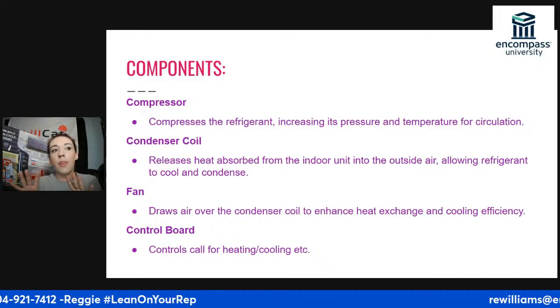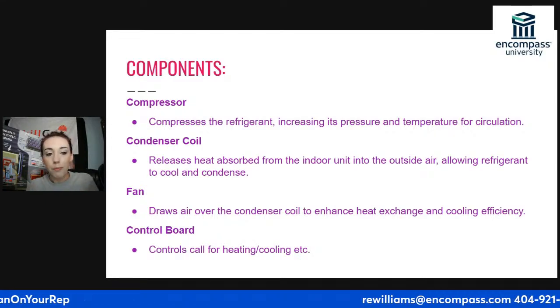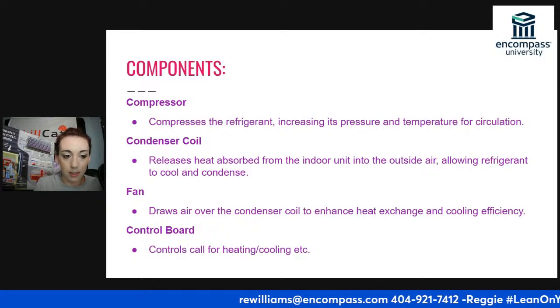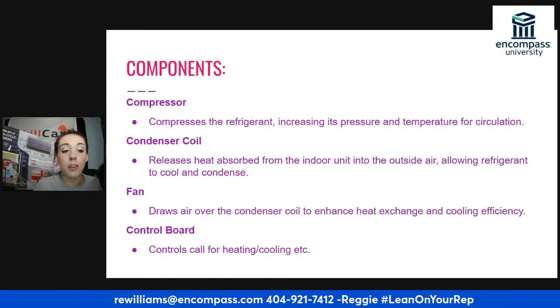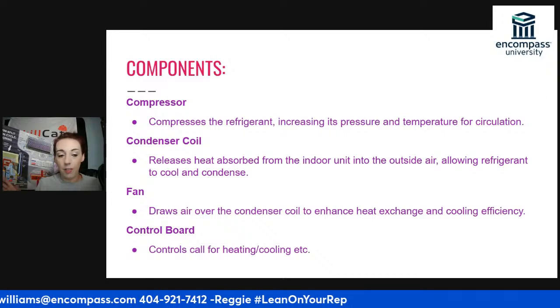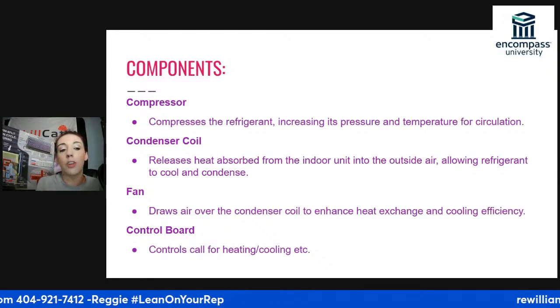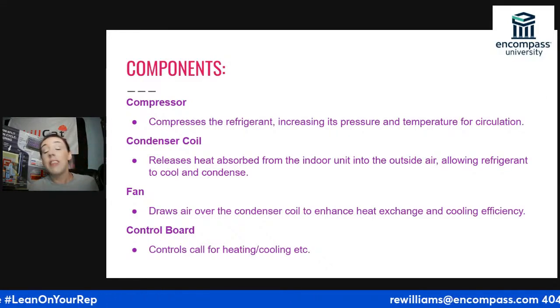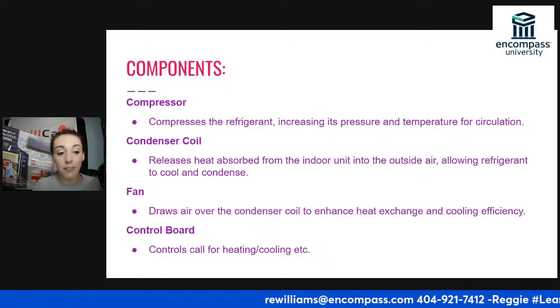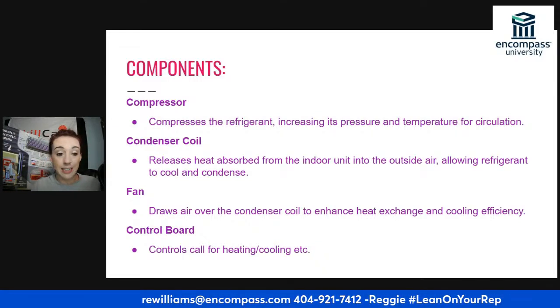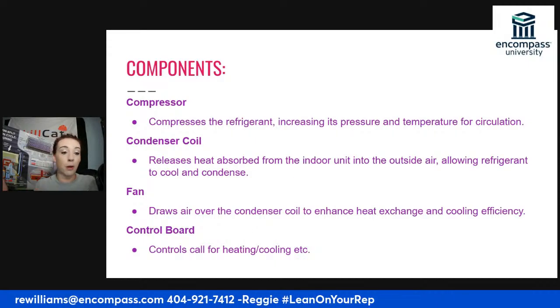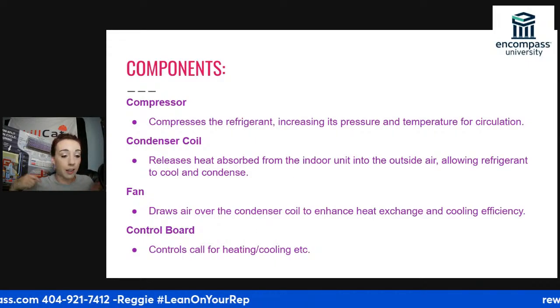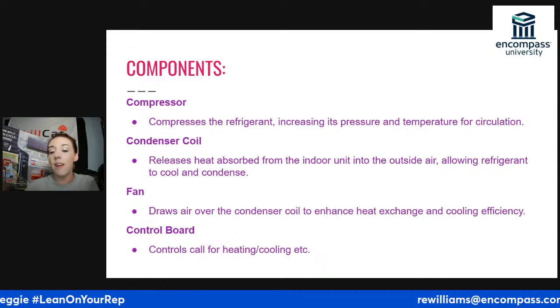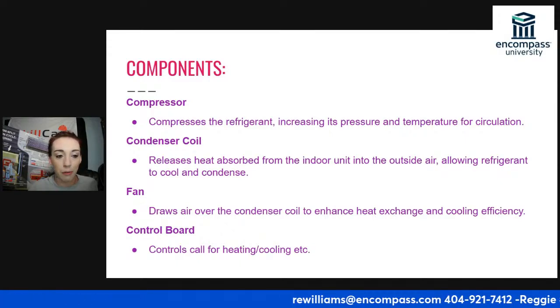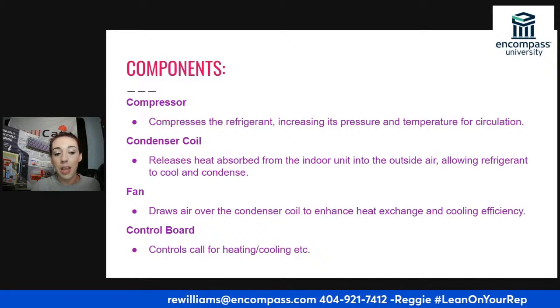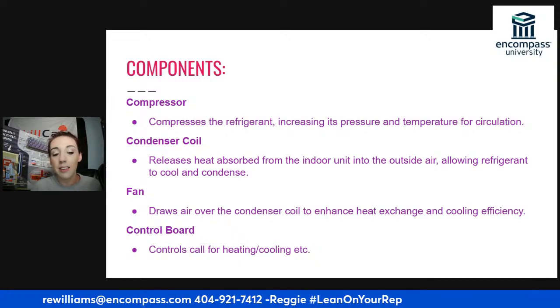The air that is hot is always going to find the path of least resistance, and the path of least resistance is always going to be to the cold. So any air that is heated is always going to be looking for a way to get to cold. So when it is 75 degrees outside and we're removing 85 degree air, or 85 degree heat, we'll say, from the indoor space, it blows out into the cold like none other. And it immediately wicks it away from that outdoor unit, never to be seen again, never to harm anybody or make anybody uncomfortable. But when it's 100 degrees outside and we're pulling 85 degree air from the space, it's a little harder to reject.